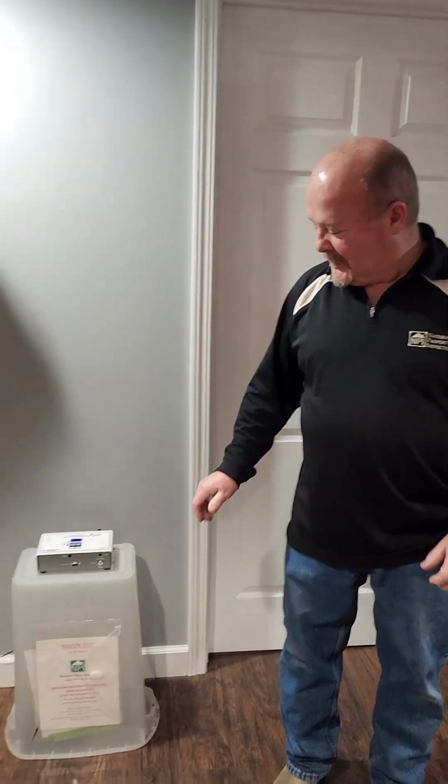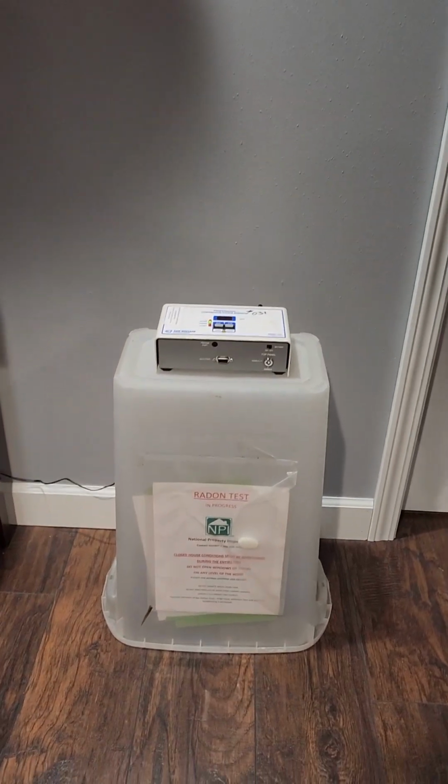So how is your machine certified to give accurate results? So all these machines are licensed with the state, and then we have a chain of custody log that we have to fill out every time we use the machine. And then we do cross testing as our control method every 10 times we use these machines, with another piece of equipment. And then once a year, these are sent out to New York, and they are put in a radon chamber, and they're calibrated. If they don't pass, they have to be repaired, and if they pass, we're good to use them for one more year. That's all part of my state licensing requirements. So we do all those steps to make sure we have an accurate reading. Okay.